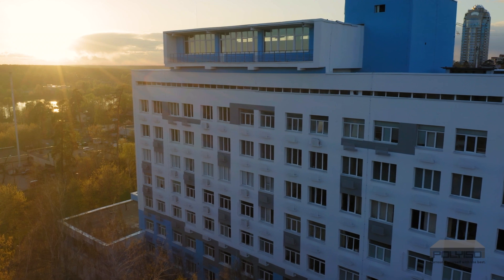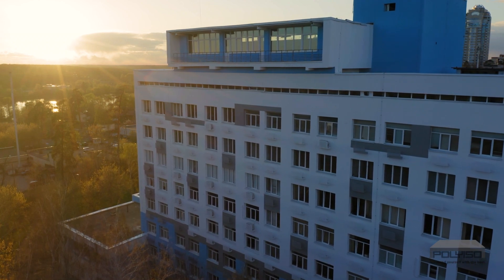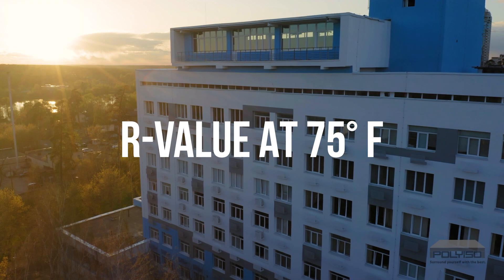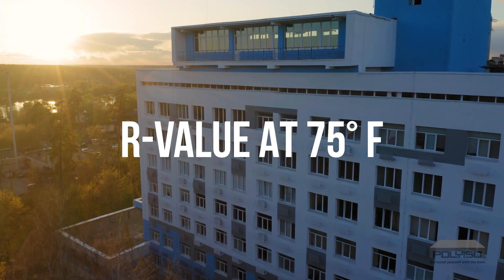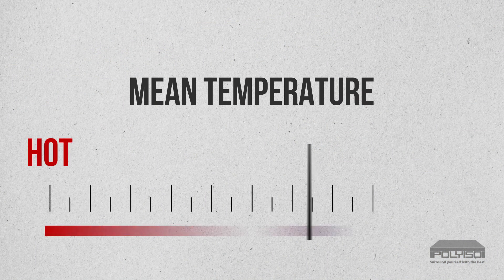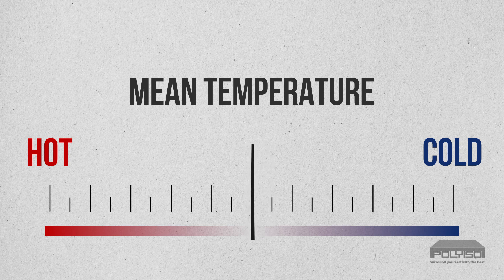While mean temperature can fall within a wide range of selected values, the material standards for specific insulation products specify the mean temperature for testing and reporting. For most insulation products, it is mandatory to measure and report R-value at 75 degrees Fahrenheit mean temperature. Mean temperature in this context refers specifically to the middle value between the hot and cold surfaces of the insulation sample in the heat flow meter.